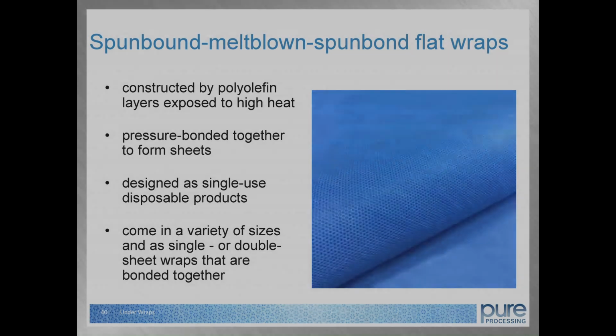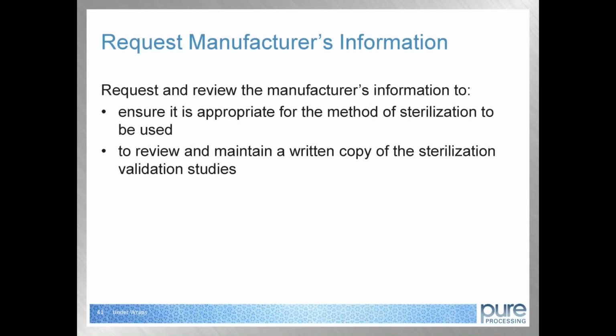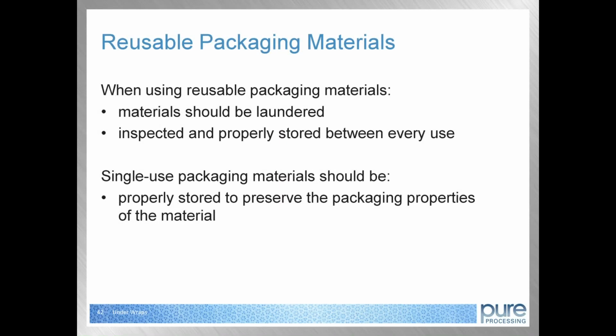When evaluating packaging materials or a packaging system, the healthcare facility should request and review the manufacturer's information to ensure that it is appropriate for the method of sterilization to be used, and to review and maintain a written copy of the sterilization validation studies. When using reusable packaging materials, materials should be laundered, inspected, and properly stored between every use to preserve the packaging properties of the material. Single-use packaging materials should be properly stored to preserve the packaging properties of the material.